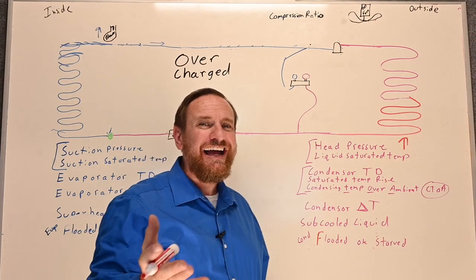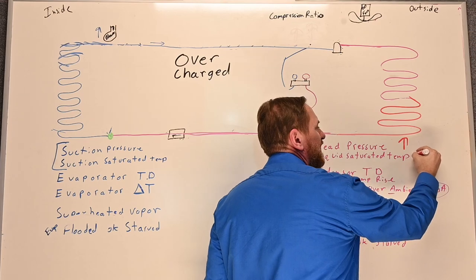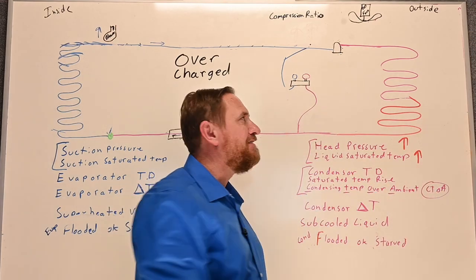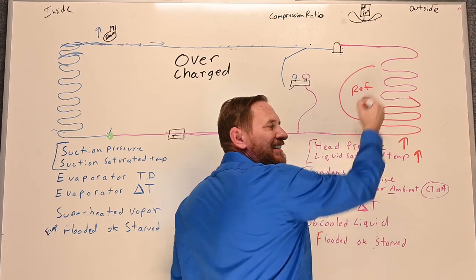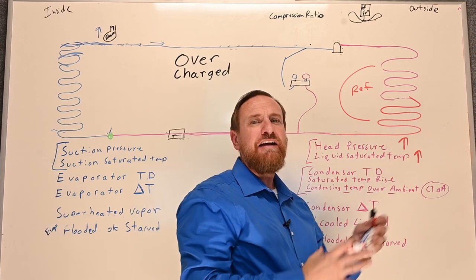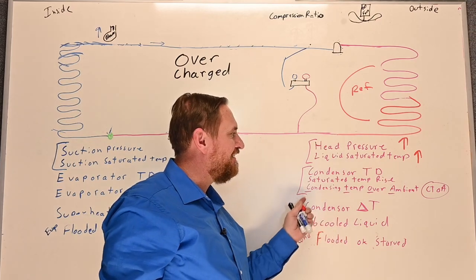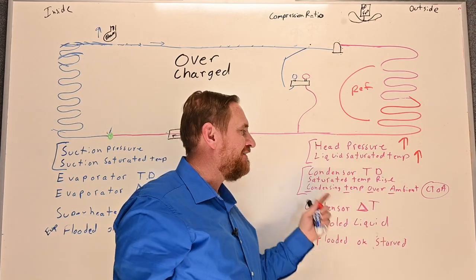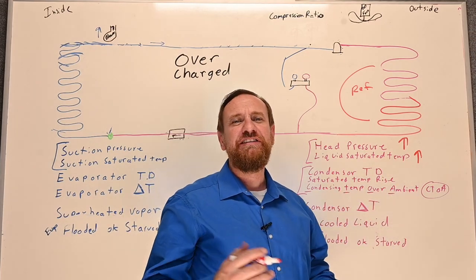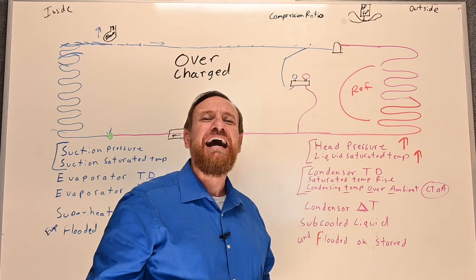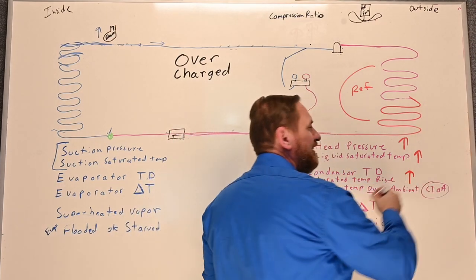What's tied to the head pressure? The saturated temperature — the liquid saturated temperature — is going to go up as well. So the temperature difference between the refrigerant condensing and the temperature of the air is going to be much farther apart. We have a name for that: it's called condenser TD, also called saturated temperature rise, or condensing temperature over ambient — CTOA. That's going to be a higher condenser temperature difference, so our condenser TD is going to go up.